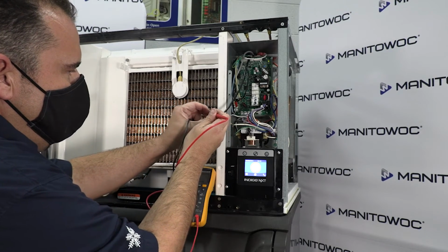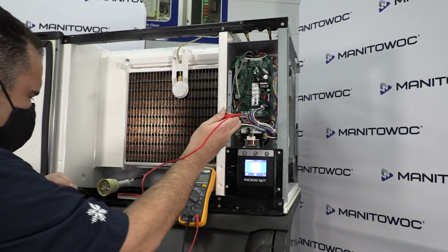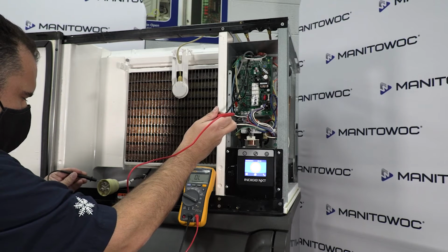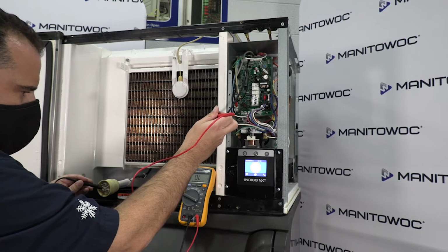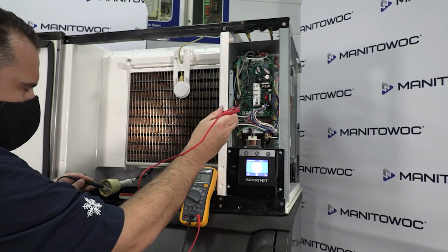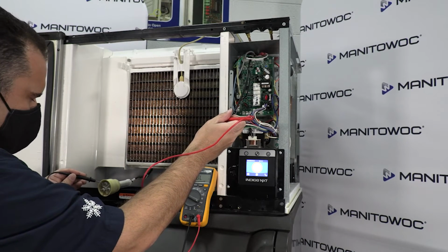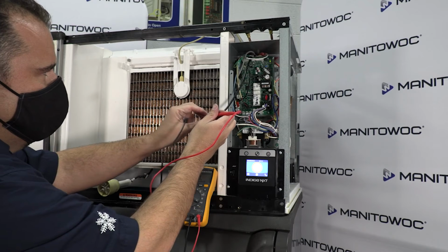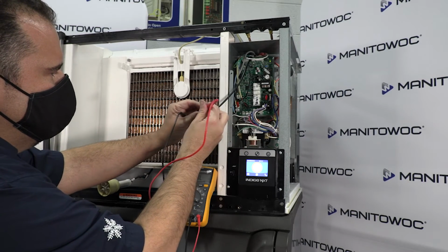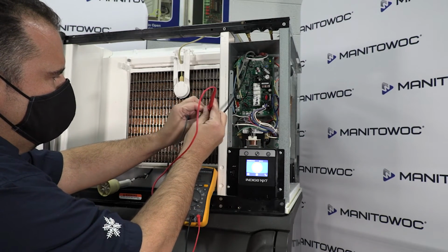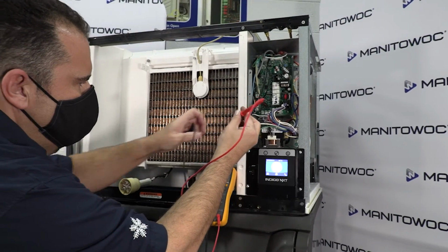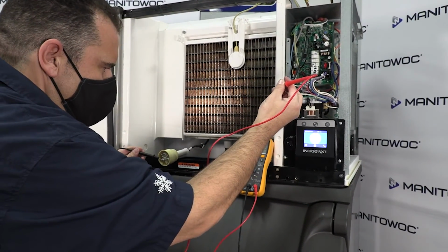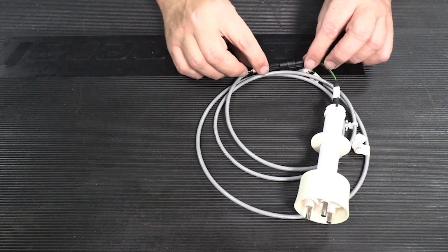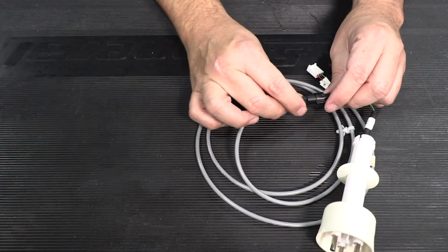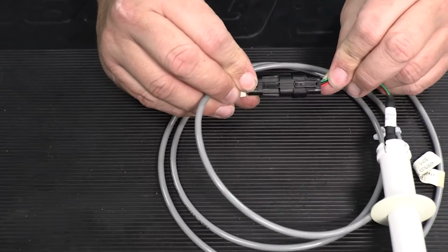Normal readings will show 0 or no resistance. However, if it does show resistance between the tip of the probe and the tip of the wiring harness at the control board, then there is a loose connection somewhere. Whether it's the probe or the wiring, we don't know. With continuity, do not change the probe. Without continuity, the probe should be replaced. Replacement water level probes come with a new wiring harness.